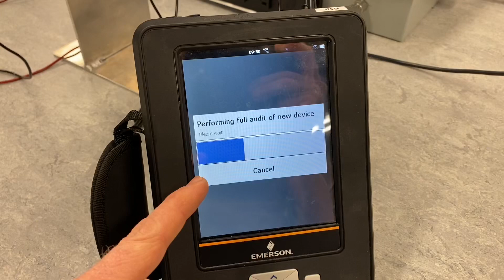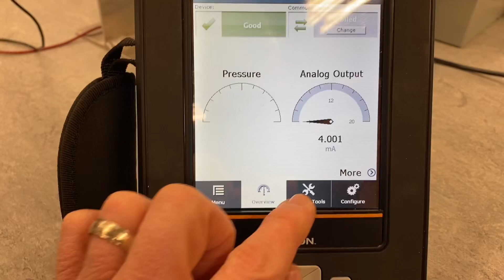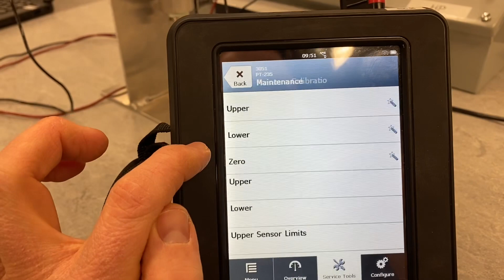It's going to scan the device and pull some information out of it. So then when we go to upload our changes that we've made to the device to our AMS device database over there, it will put the information with the right tag. So now that we're connected, we can go to Service Tools, Maintenance, and we're going to do pressure calibration, and we just want to do a 0.